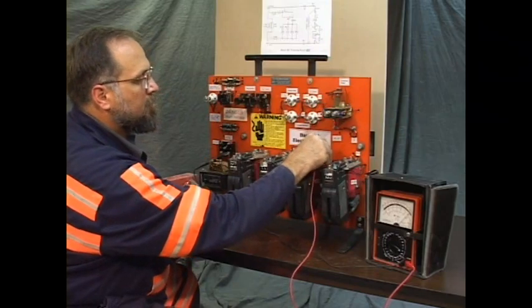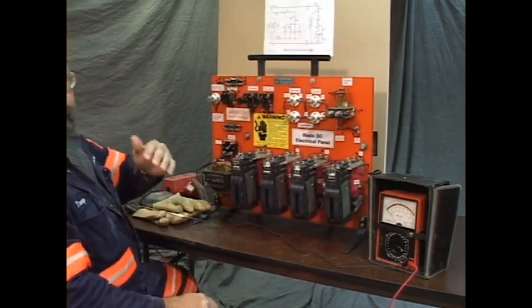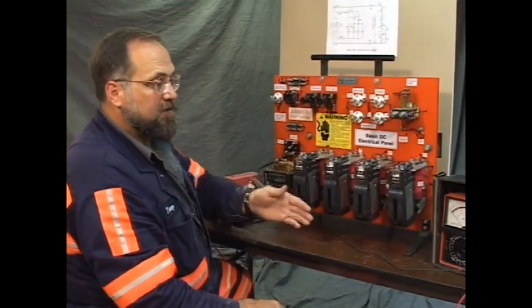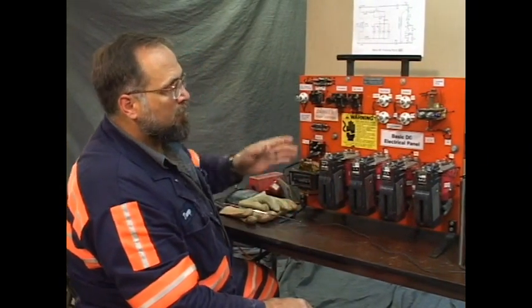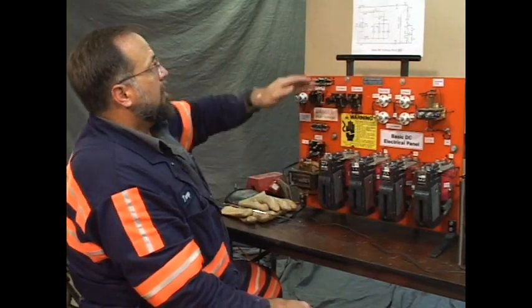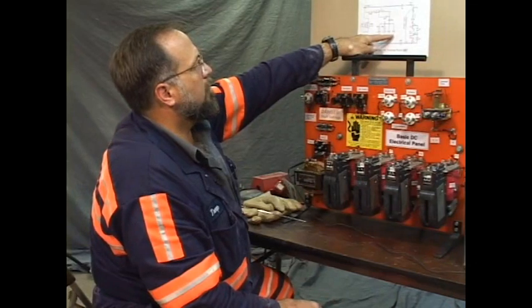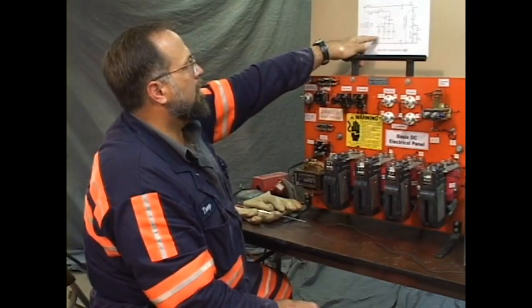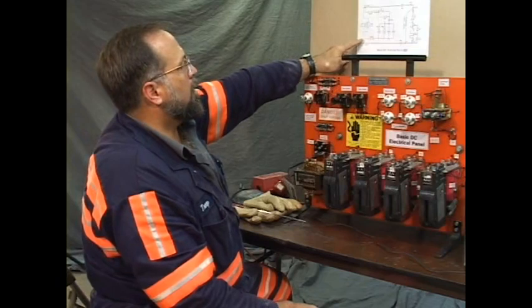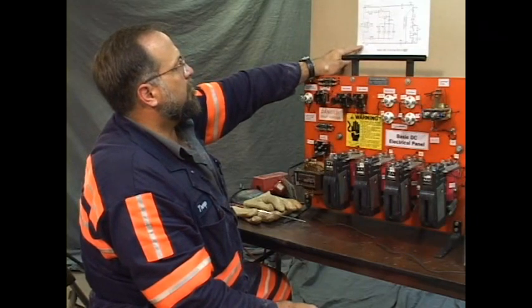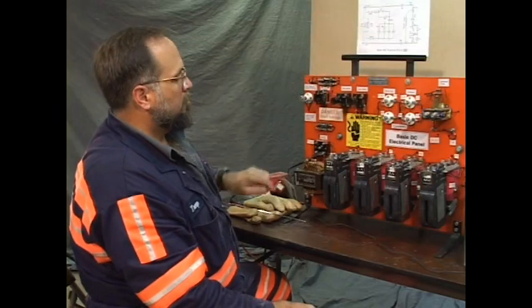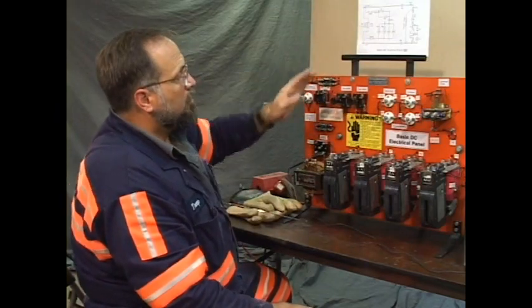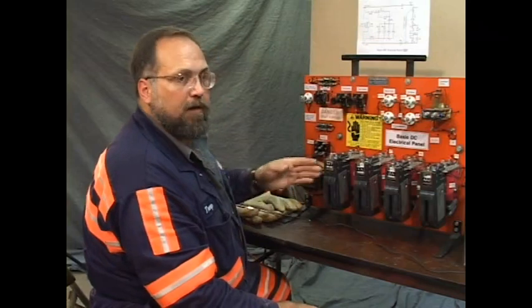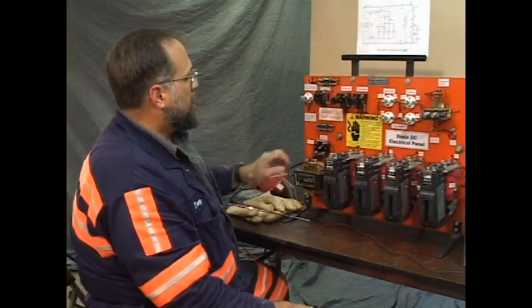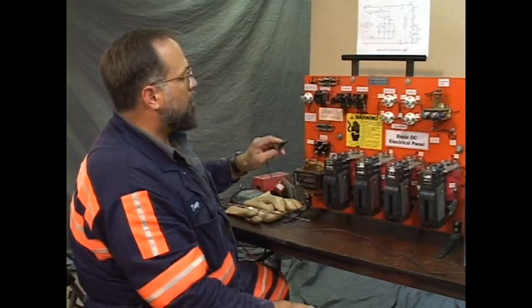That's good. And if you recall, through the problems that we talked about earlier, we had symptoms. We tried the panel with power on. We saw the malfunction exhibited in the lights. And we had an open return wire, negative wire on M2, M1, 1A, and 2A. We had an open wire from the rectifier to the top front of M1 or M2 contactor. We had all those points. Had any one of those existed, we would have found it just now. Okay, let's move on to the power portion of the print.